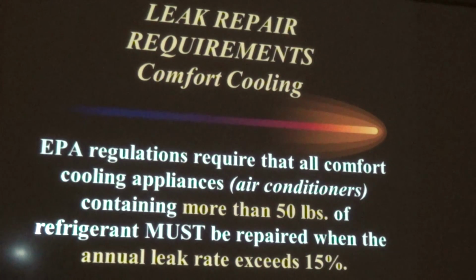Now, there was no leak requirement under the law for type 1 appliances, but that's not the case for type 2, and will not be the case for type 3. Here comes the law. The law is the same for type 2 and type 3. So if you learn the law for type 2, it's the same for type 3. There's going to be two parts. The EPA requires that if it's a comfort system, cooling appliance, meaning an air conditioner, that holds more than 50 pounds of refrigerant, it must be repaired when the annual leak rate is more than 15%. That's the first part of the law.